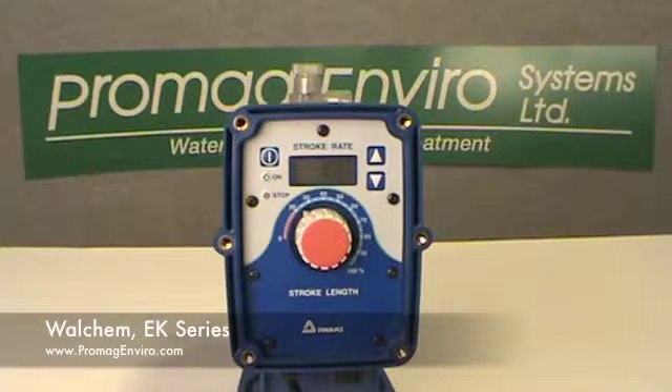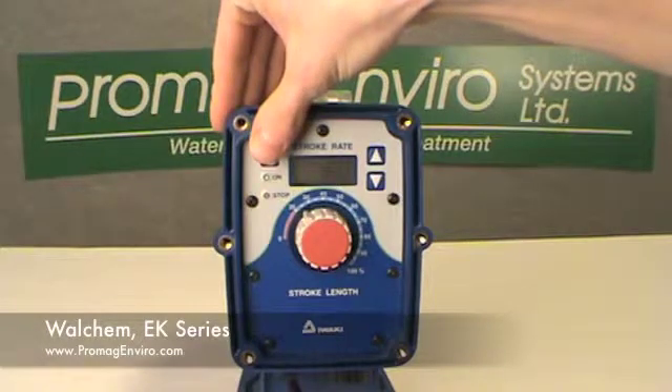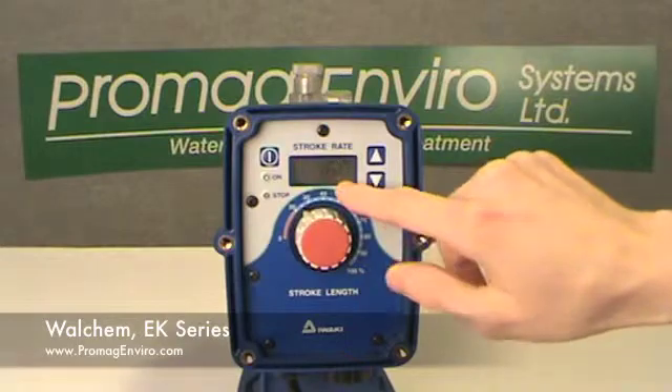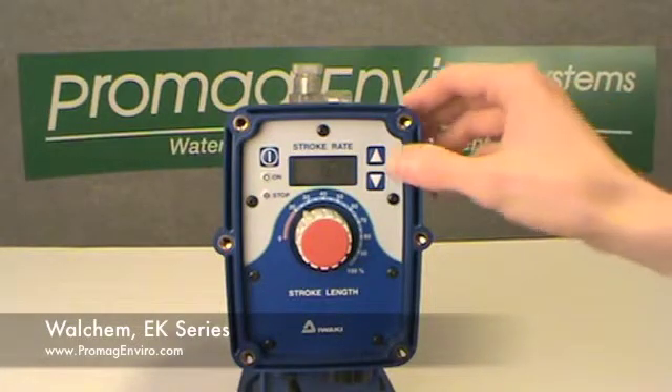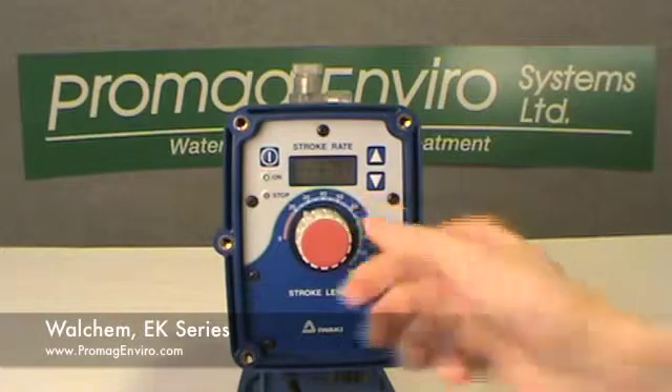The pumps can be operated manually by pressing the start-stop key from the wait mode. Once pressed, the pump will begin to operate at the stroke rate shown on the display. From here, the up and down keys can be used to change the stroke rate, and the stroke length knob can be adjusted down to further reduce the pump output.